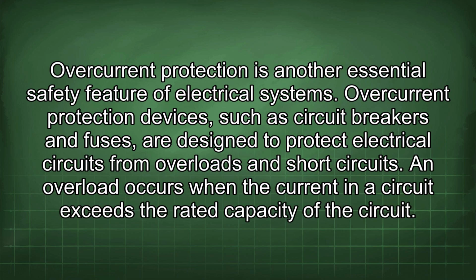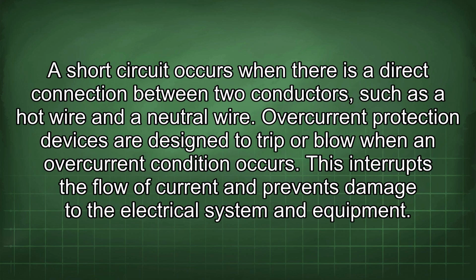Overcurrent protection is another essential safety feature of electrical systems. Overcurrent protection devices, such as circuit breakers and fuses, are designed to protect electrical circuits from overloads and short circuits. An overload occurs when the current in a circuit exceeds the rated capacity of the circuit. A short circuit occurs when there is a direct connection between two conductors, such as a hot wire and a neutral wire. Overcurrent protection devices are designed to trip or blow when an overcurrent condition occurs. This interrupts the flow of current and prevents damage to the electrical system and equipment.